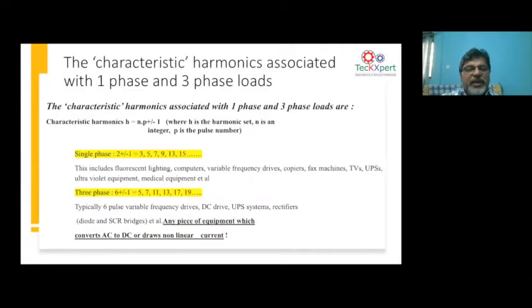The next one. Anything when you go into power quality, the very fundamental approach is to characterize it. As I said in the very beginning, the IEEE 1159 standard is also trying to characterize the power quality phenomena, whether it's a transient, an oscillation, or harmonics. You need to characterize it. So when it comes to characterizing harmonics, how do you do this? Number one, it will have certain harmonic frequencies, and then it also will have the total sum of all those frequencies. So that is how you characterize it.